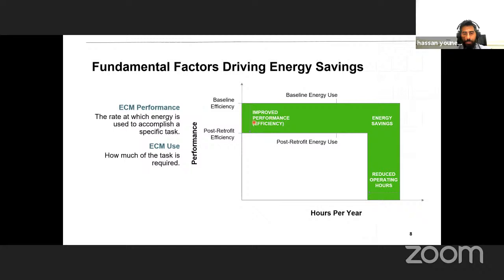On this side, this is mainly due to improved performance efficiency. We had a COP of, let's say, 1.8 kilowatts per ton, and now we've gone down to an annual efficiency of, let's say, 1.2. So there's a good amount of difference between the old inefficient chiller and the new one. These savings are mainly coming from the improvement of efficiency, whereas the other savings come mainly from reduced operating hours.